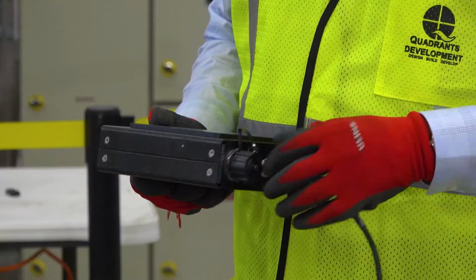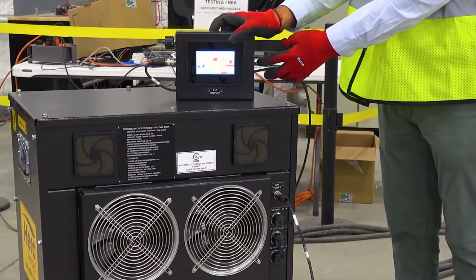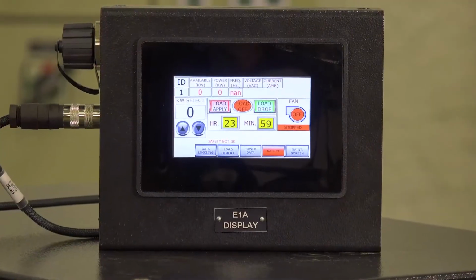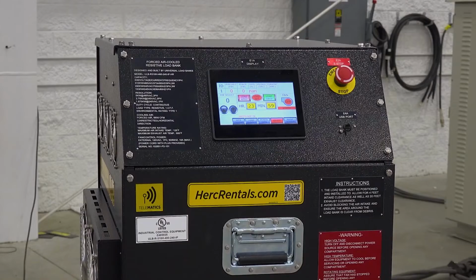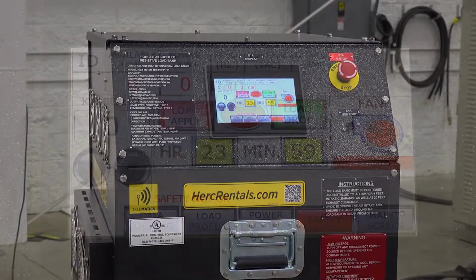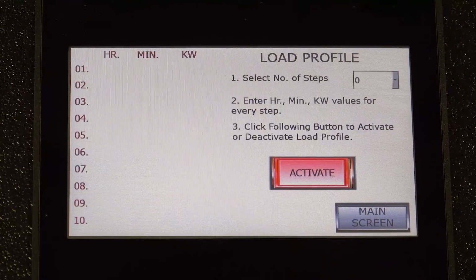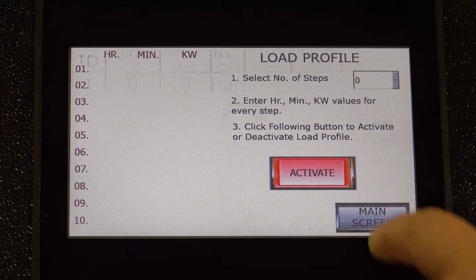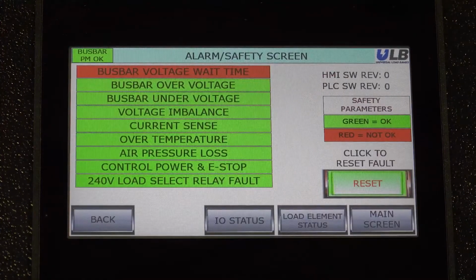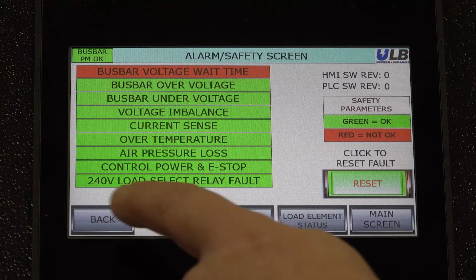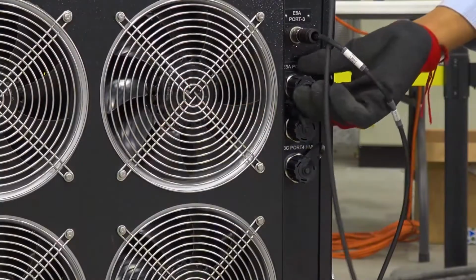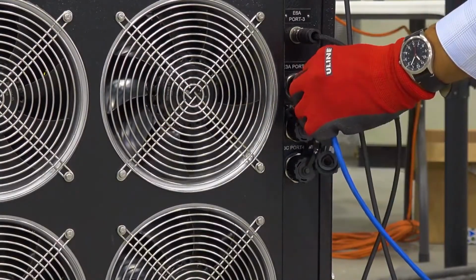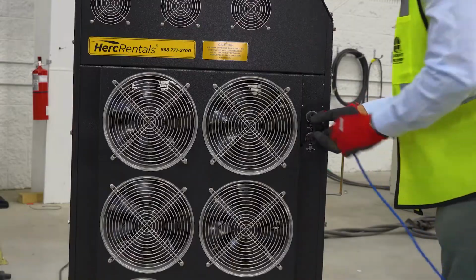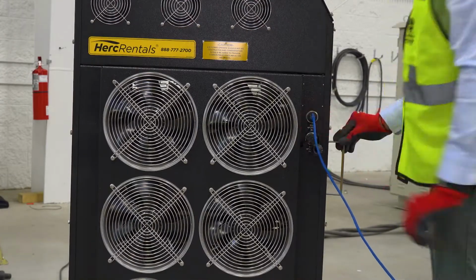ULB utilizes an HMI PLC control network which allows the user to monitor and control all the functions of the load bank. The ULB control system also allows the user to preset up to 10 load profiles and automatically stops and starts when activated. Standard safety features include air fail, overtemp, phase loss, overtemperature, and hardwired ESTOP. ULB load banks can also be networked up to 14 units at a time to increase the overall load capacity.